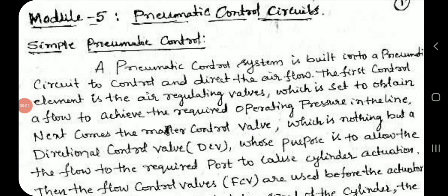Module 5: Pneumatic Control Circuits. A pneumatic control system is built into a pneumatic circuit to control and direct the airflow. The first control element is the air regulating valve, which is set to obtain the required operating pressure in the line. Next comes the master control valve, which is a directional control valve whose purpose is to allow flow to the required port to cause cylinder activation.